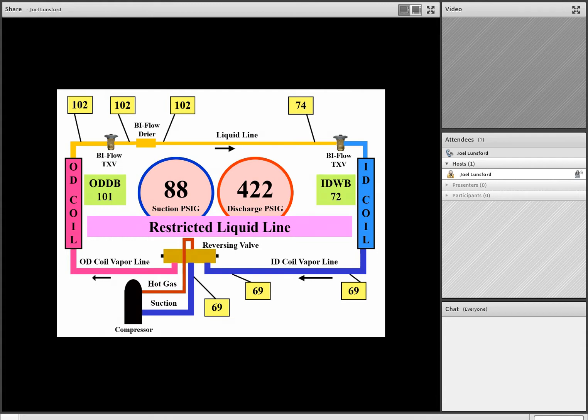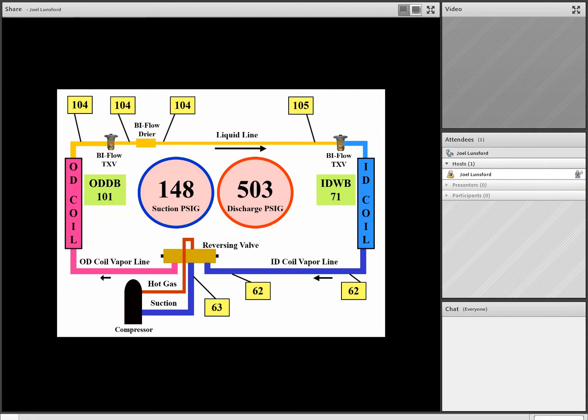Let's do another example here. Here we have a 410A unit with 148 pounds of suction pressure. As we take a look at our pressure temperature chart, 148 pounds of pressure gives us approximately 53 degrees. So we take a look at our indoor coil vapor line, and we see that we've got 62 degrees. Well, the difference between 53 and 62 is about 9 to 10 degrees of superheat. So the indoor coil is normal in this service call.